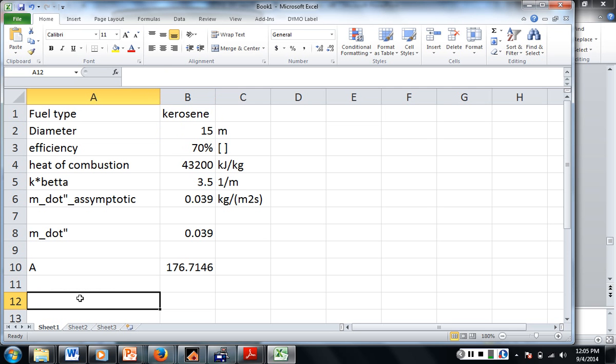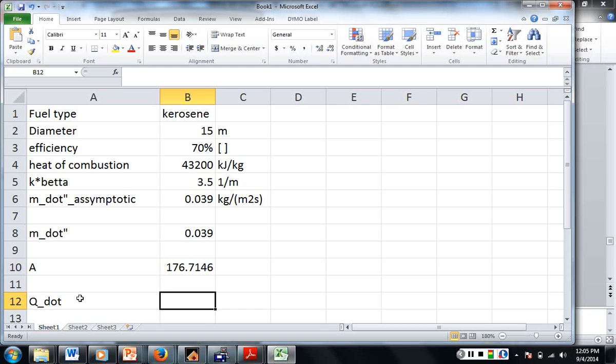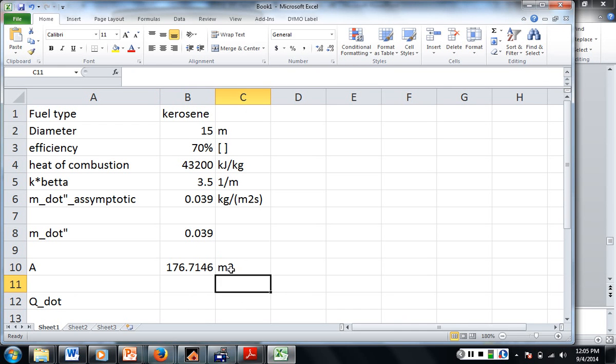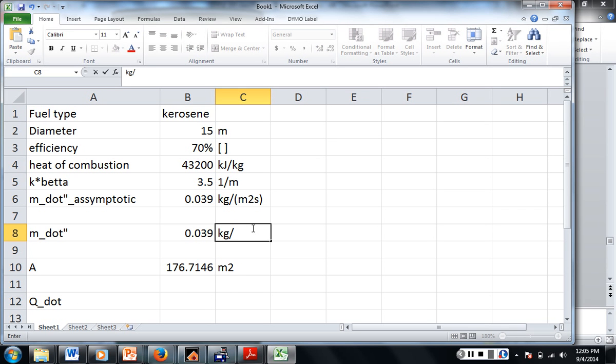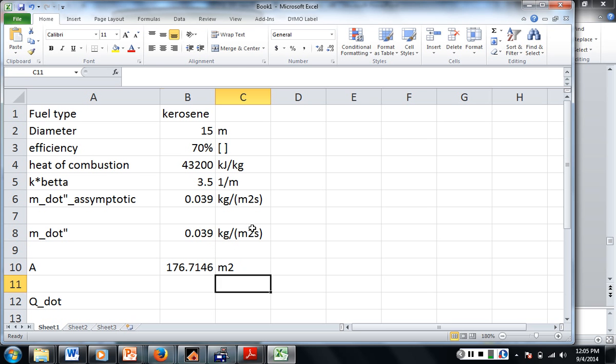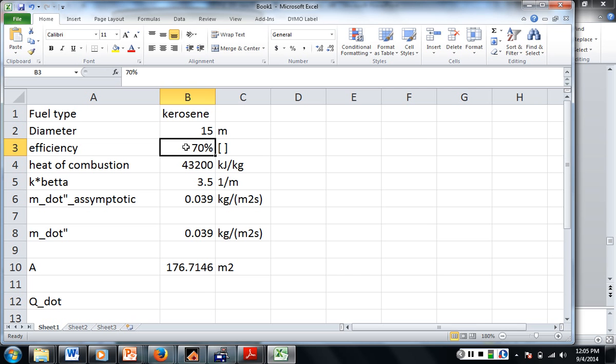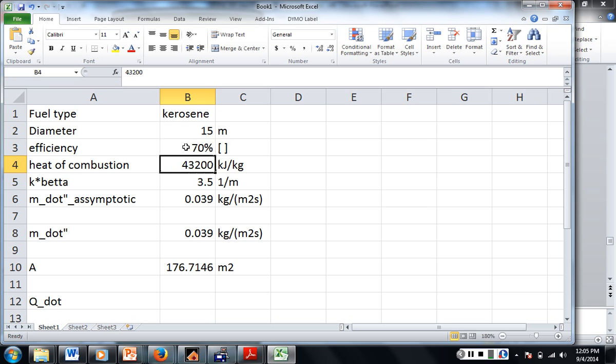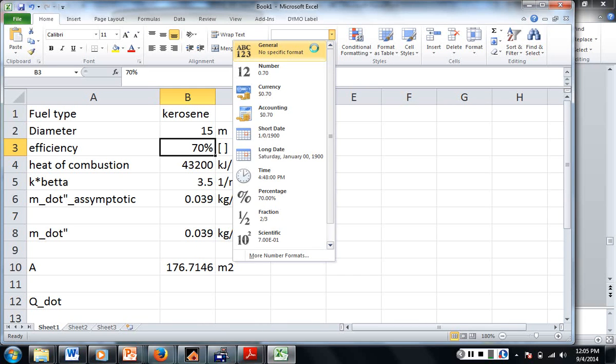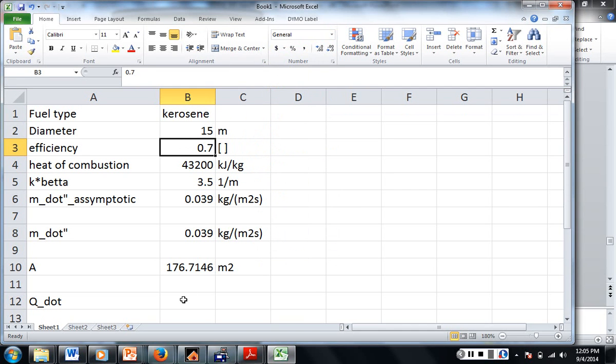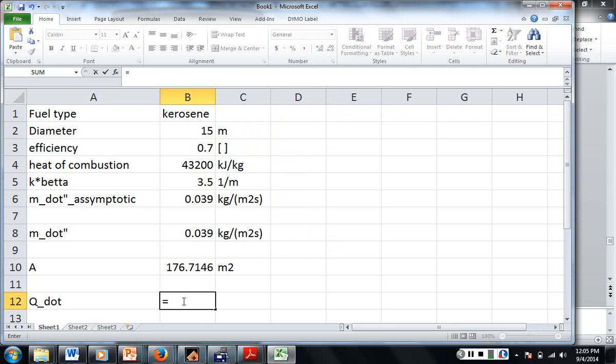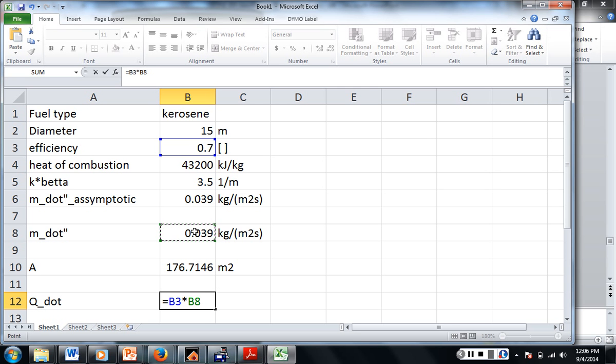And so then, our q dot, our heat release rate, this is meters squared. I always like to write the units if I can. Kilograms per meter squared second. So our q dot is going to be equal to... Oh, we need to put the efficiency in as a decimal. So we'll make it 0.7. Not percent. Ah, nuts. I just want a general number. Alright. So 0.7. So this is equal to the efficiency times the mass flux times the surface area times the heat of combustion.